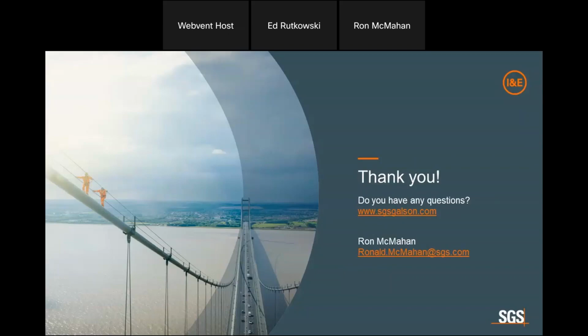Okay. Another question from Luis having to do with the frequency of calibration. He asks, is it worth calibrating instruments on an annual basis if they're old, say from the 1990s, and outdated? Yeah, I would say it depends on the sensors. When you look at sensor technology today, what we use in this instrument, infrared CO2 from AlphaSense, electrochemical AlphaSense CO sensor, temperature, humidity, the PM sensors, the expected life on these things, except for PM, could easily be 5 to 10 years and longer. Because we're in an indoor environment and we're not exposing this to extreme environments and high concentrations of gas, we should not typically see a dramatic shift in output.